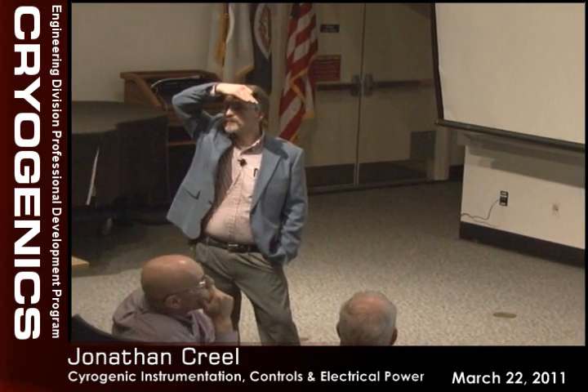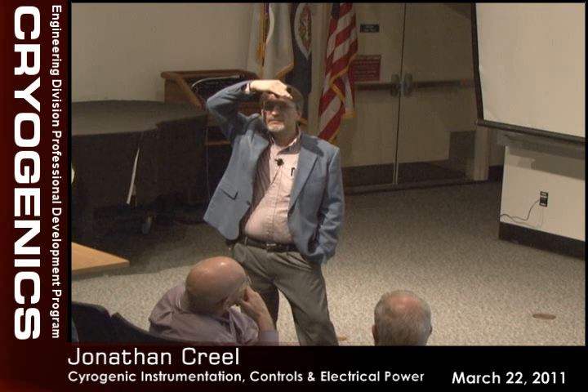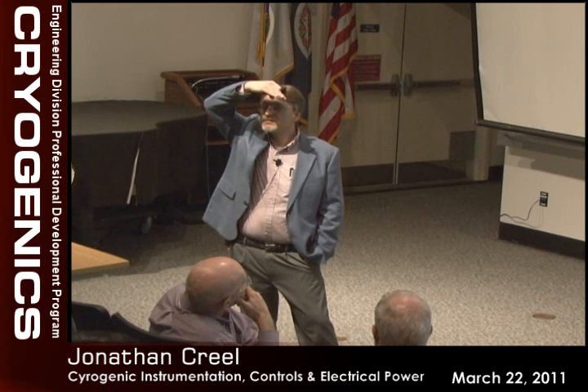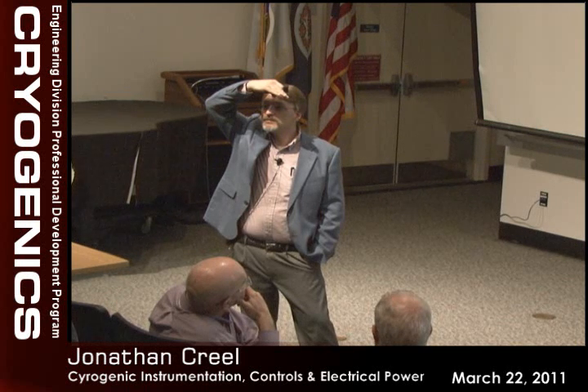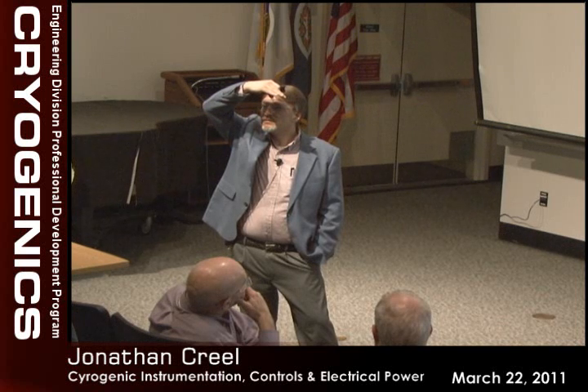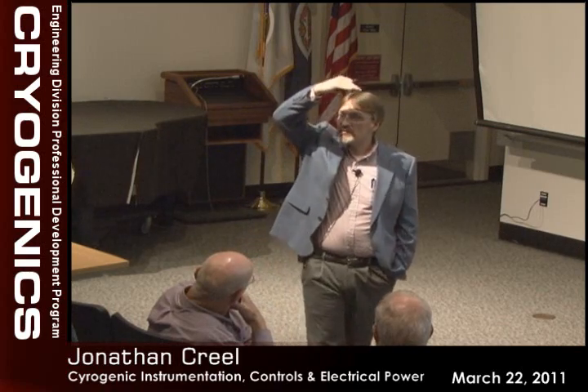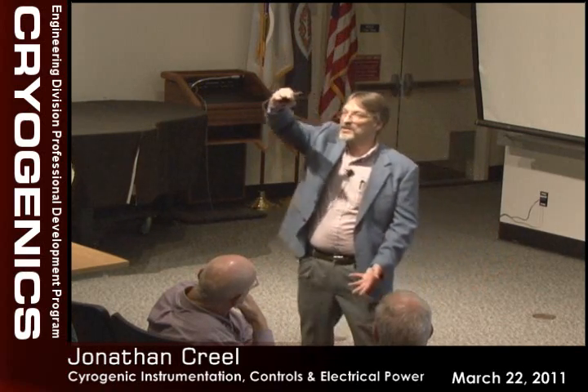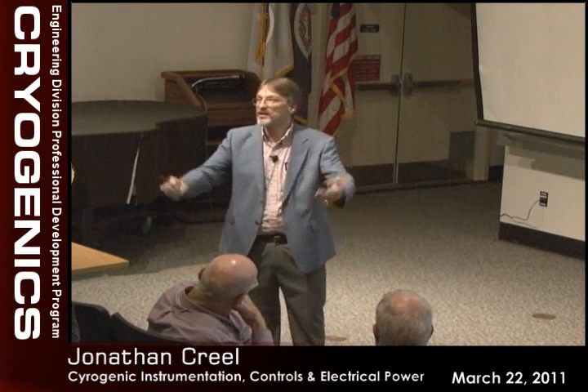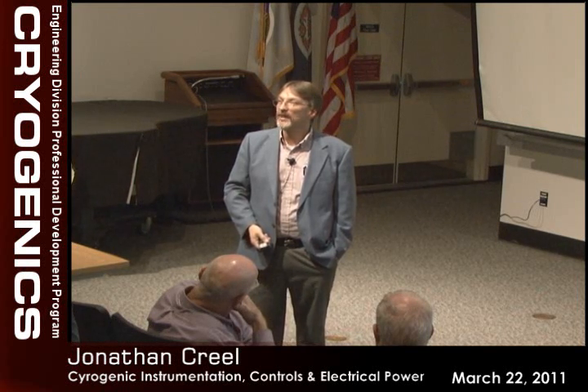I've seen one on a hydrogen tank which looked like a tape. And they measured the change in the impedance. Yeah, that's how the superconducting probes are made. You have basically a piece of superconducting wire hanging down inside the liquid, and as the liquid level comes up and down, it changes the resistance of the probe. It wasn't straight up and down, they wrapped it around the tank, so they had 500 feet of it on the tank. Wow. I haven't seen that.